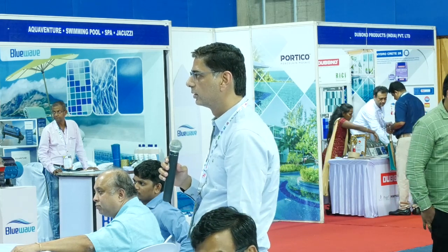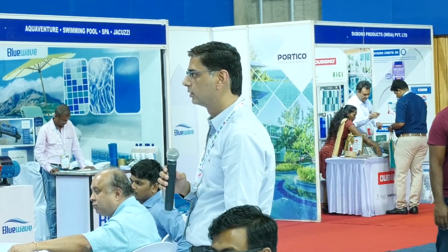See, why do we filter? Because we anticipate that the water will get polluted. It is polluted because of the use. Now in public pools, you will see that at a time 50 people, 40 people will take a bath. And what pollutes is sometimes a little bit of urine, sweat, saliva, and all these things, they always pollute the water. So the more the load, the faster the purification, the shorter the purification time. For private pools, you can do once a day, 4 to 6 hours is sufficient.